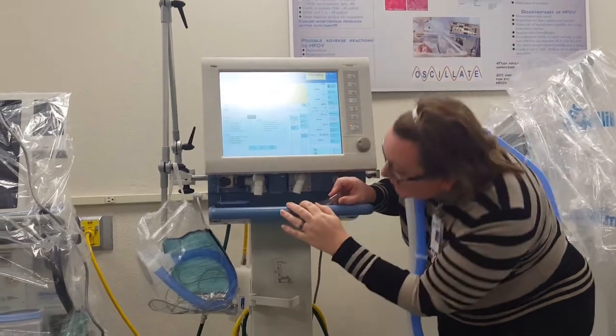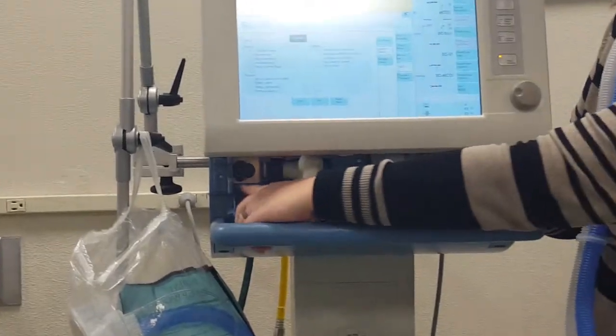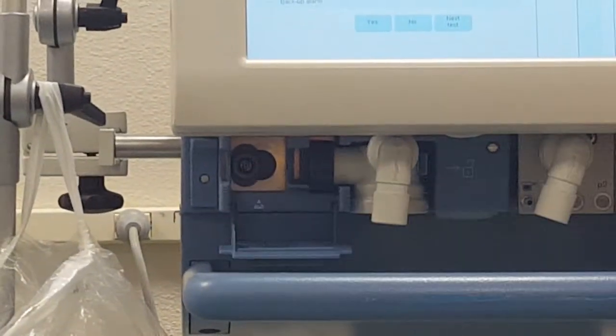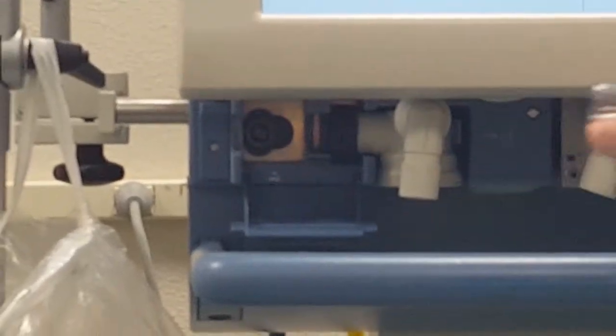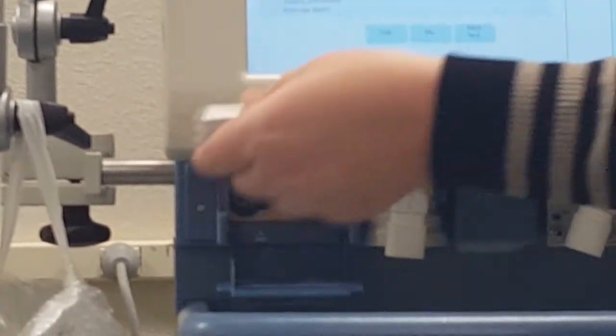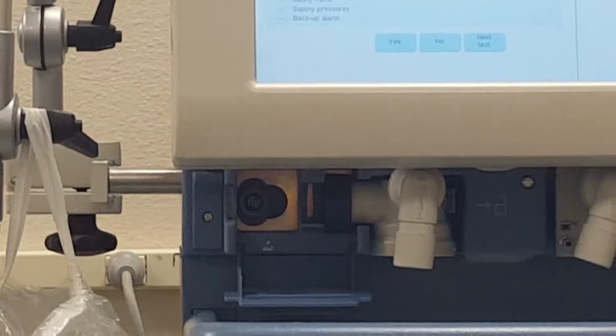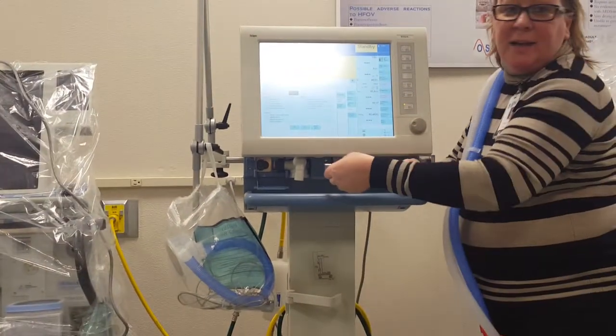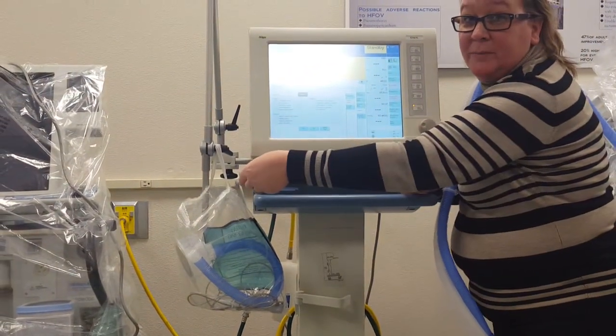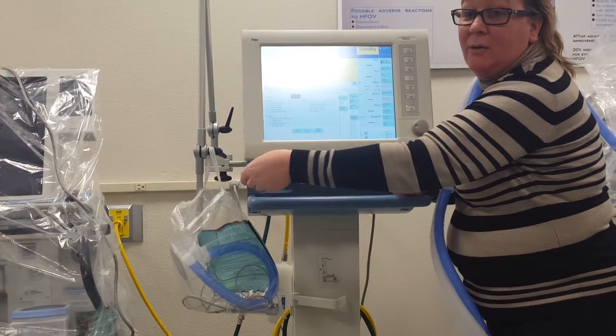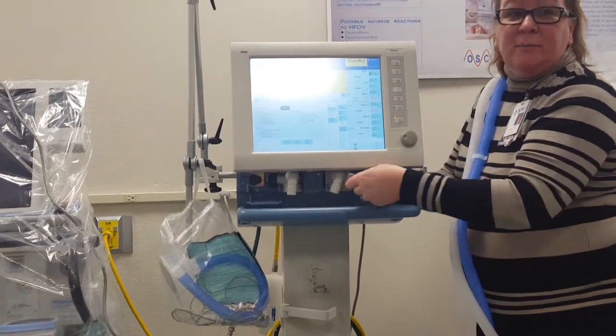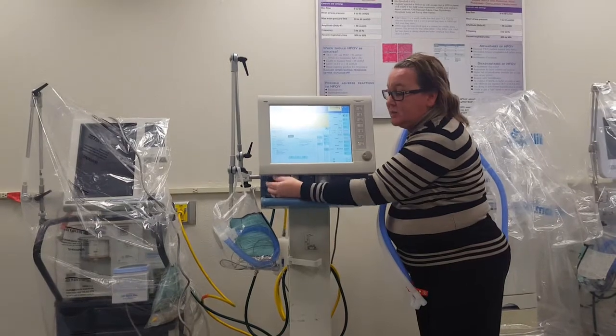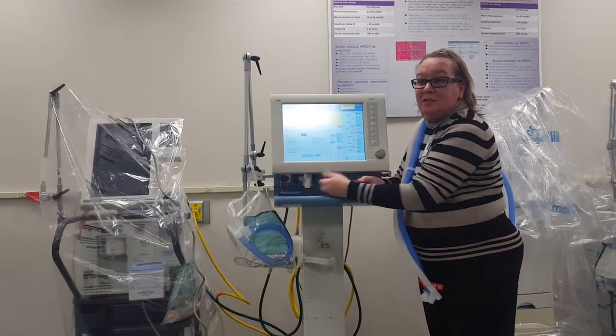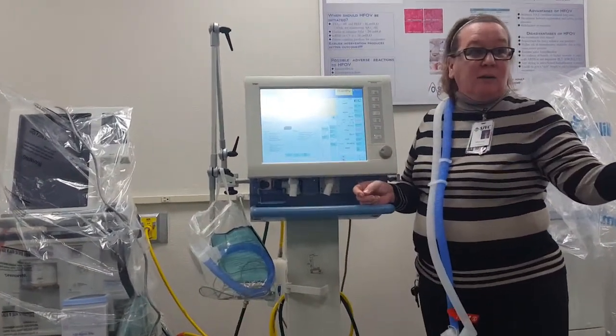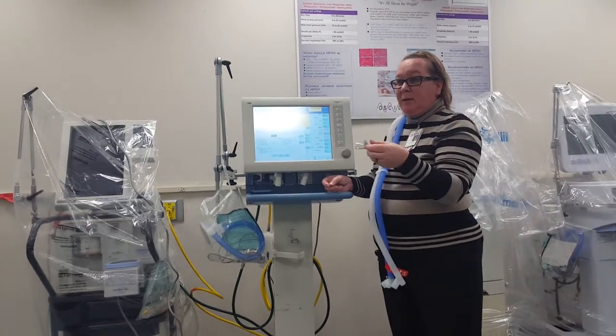When you push this in, there's a little flap here, and then there's a little spot where this can sit in. We're going to push it in and then slide it over. Because it's slid into place, when you take the exhalation valve out, you actually have to slide this back over first. It sits right in the exhalation valve, so if you don't do that, it's going to make this fly across the room and possibly break.